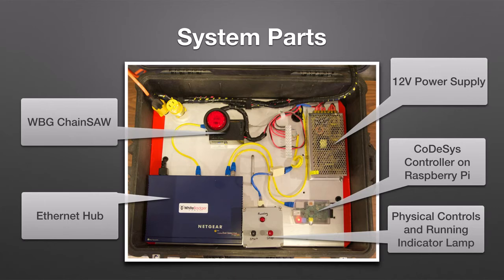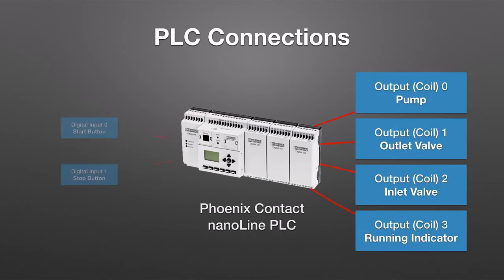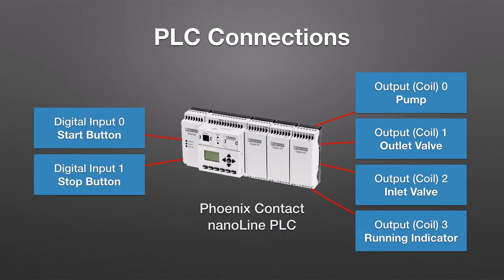Taking a peek behind the curtain, let's look more closely at how things are connected and what's actually being done. The heavy lifting of device control is done by the Phoenix Contact NanoLine PLC, which uses its internal relay outputs to control power to the pump, valves, and running lamp. It also accepts the physical start and stop button inputs.